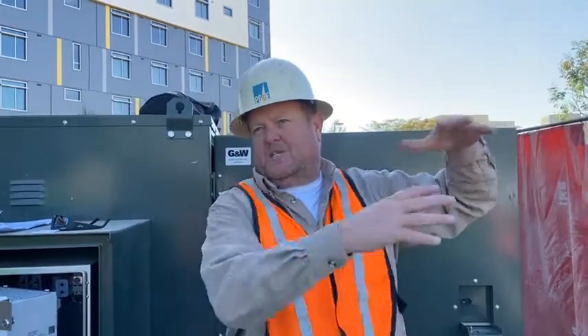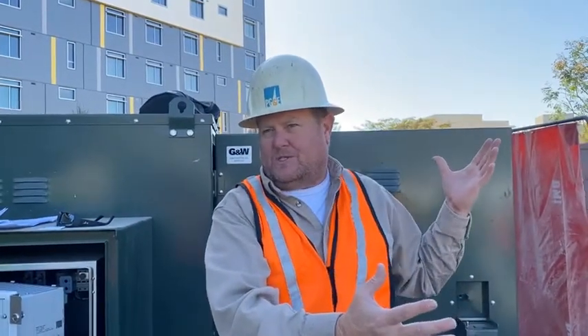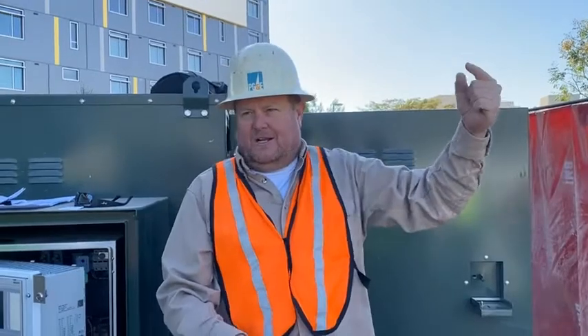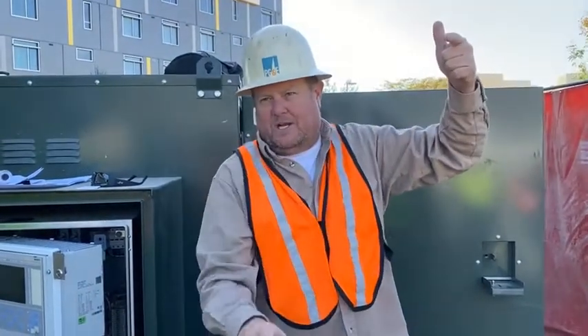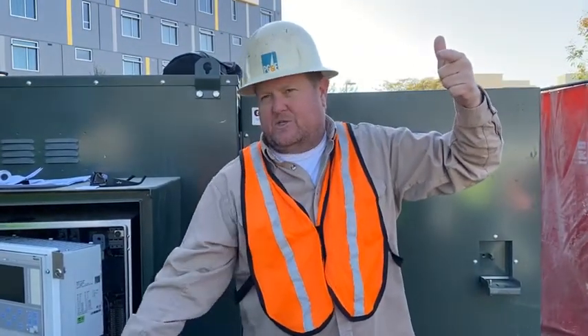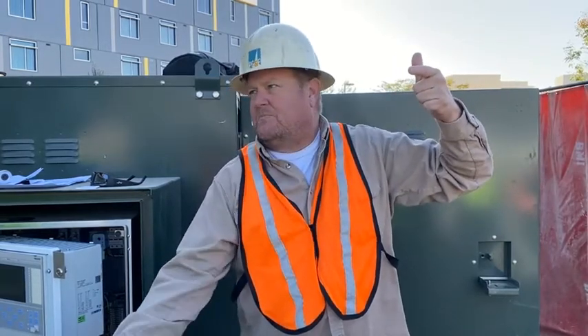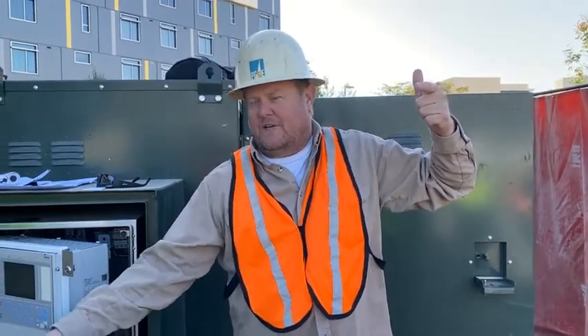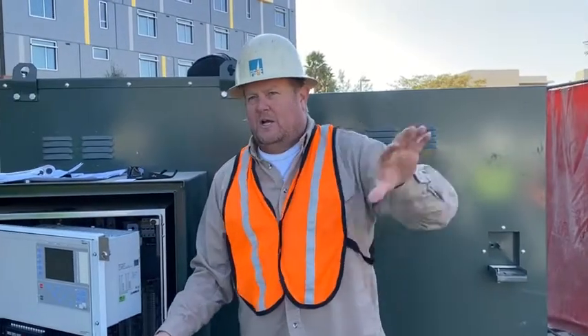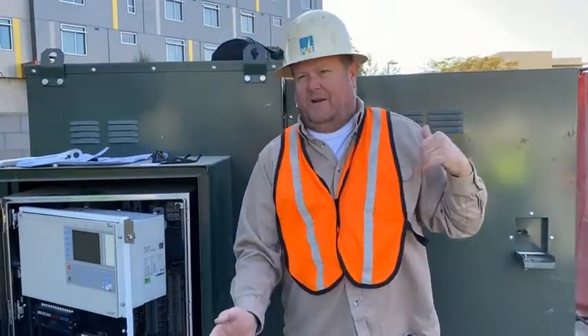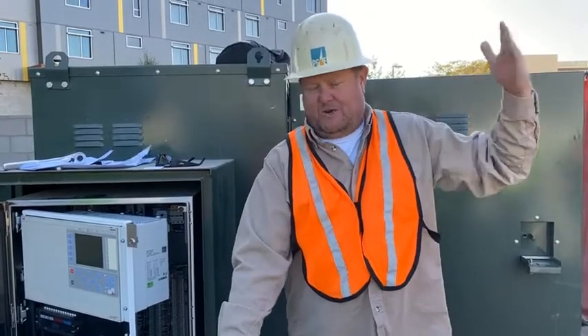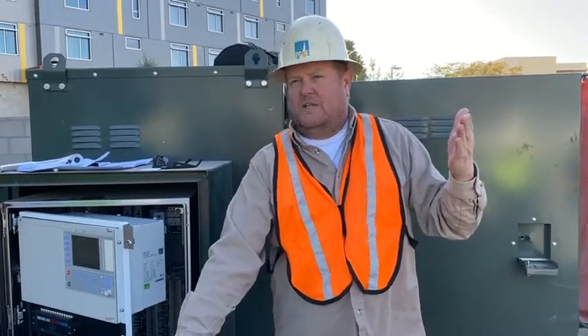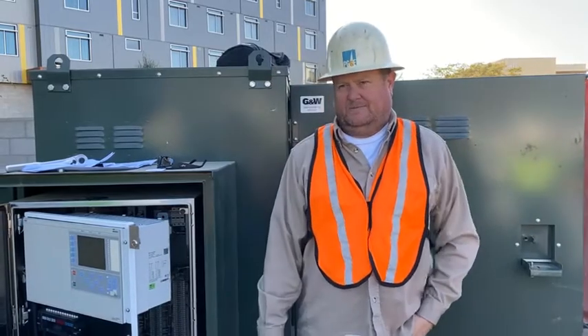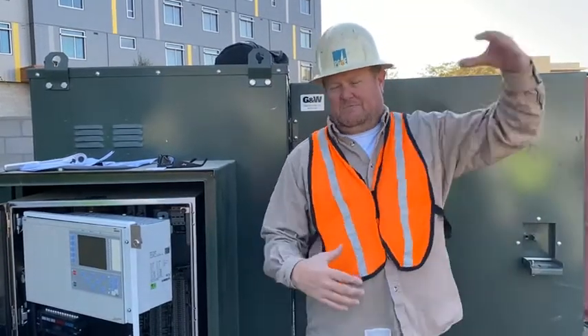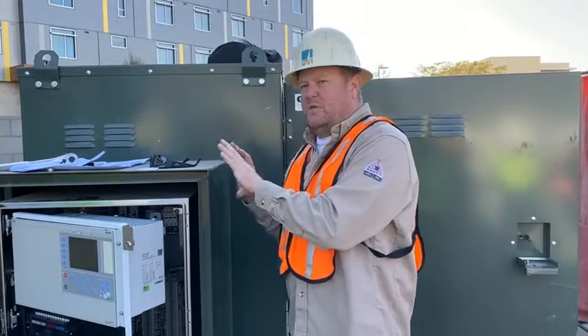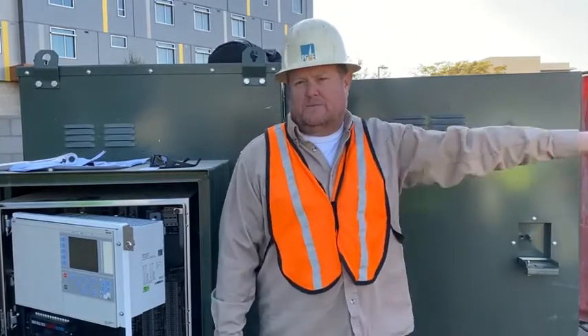Now, that's going to initiate all of the logic in the control scheme to go, all right, I tripped my feeder breaker. And it's going to start going back, talking to each of the switches, seeing, okay, the fault was in between switch 4 and switch 5. Open that switch, okay, close feeder breaker. It's going to reclose the breaker and re-energize that loop, isolating that segment. So it's not just the switches, but you actually have to control those feeder breakers.